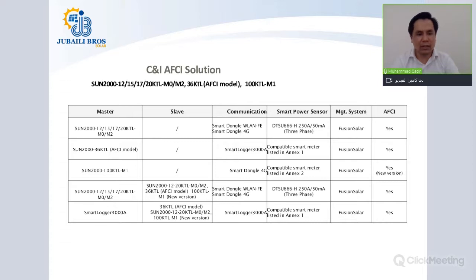In the AFCI scenario, Scenario 1, where you are using a 12 to 20 kilowatt size of inverter and no slave, you have the communication option through WLAN-FE and 4G dongle, and a smart power sensor you can use from Huawei itself, and the management platform is FusionSolar. Scenario 2, if you are using the 36 KTL with the optional feature of AFCI, with no slave device, you have the communication option using only the 3000A smart logger. And for the power meter, refer to Annex 1, which I will be speaking about at the end of this webinar.